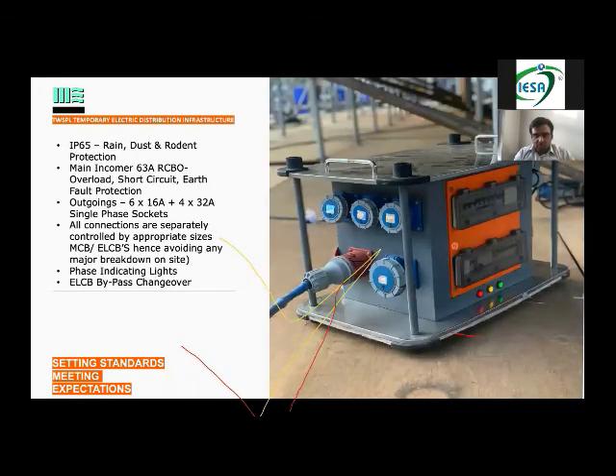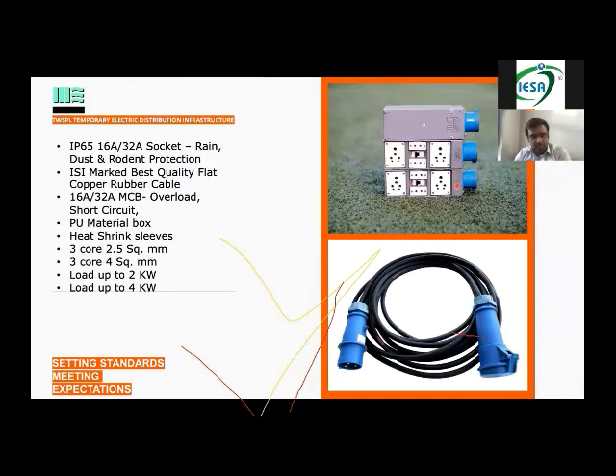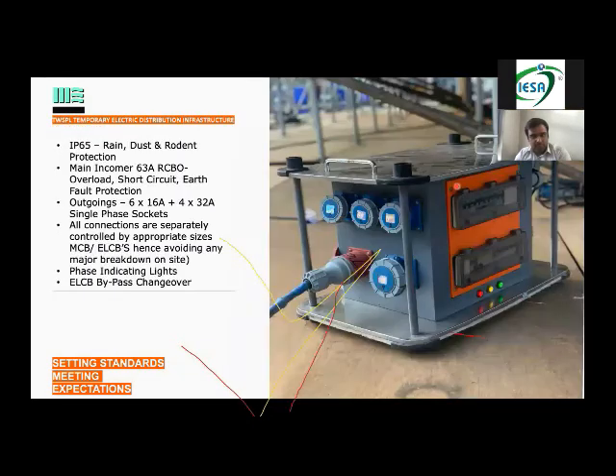This is my smaller panel. So from the main panel, we give power to this smaller panel. Over here, there are different sockets. So if you have 500 plug points on site, we're not making any circuits. Every socket is controlled by its own MCB. Then we lay a wire, and one single plug point is given to each and every activity. Let it be 1,000 plug points on site. Why? Again, it is easier to identify a fault. If something goes wrong, everything is not going for a toss.